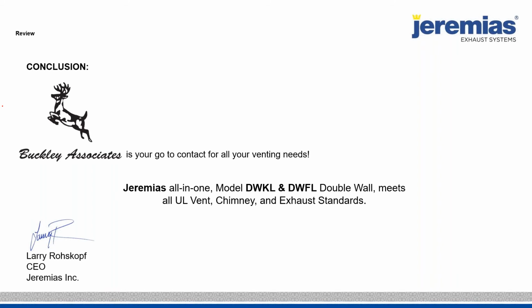Okay. So in the case of an exceptionally tall stack, through a high-rise building or whatever it is, where I have much more draft than I need and want, do you have a draft control system or damper, or would that be a different product? No, we do have a draft control system we add on. We take a look at every job. We recommend that we do it before you put it out on the street. So just have us go to your Buckley person, and we have our tech team take a look at it. If it needs the modulating damper, we offer that, and you get all the data sheets when that's sent back to you. Yeah, we do a lot of the damper systems because we have to make sure that we're providing the complete system for the engineer and also for the representative.